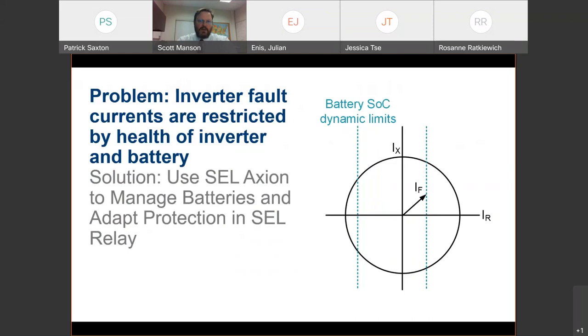Let me say it again. So now AC protection systems, SEL relays, have to adapt to failures of a battery here and there. And it may not mean your inverter's down. It may very well be that just a few batteries are offline. So what we do at SEL is put Axions and RTACs and electronics onto battery systems to provide real-time advisement to protective relays so that we can adapt very quickly to changes in battery health. This is a serious issue.